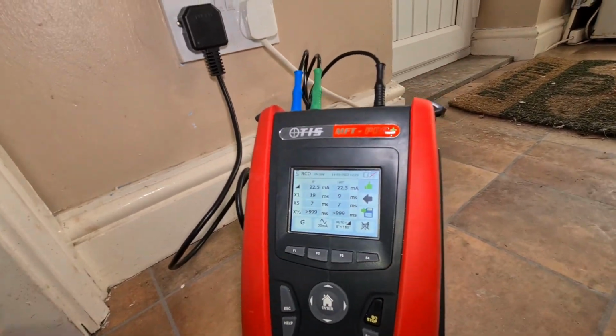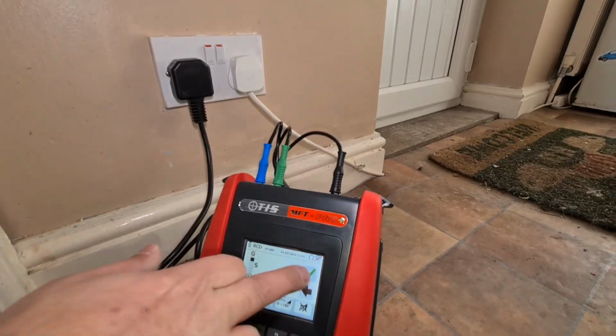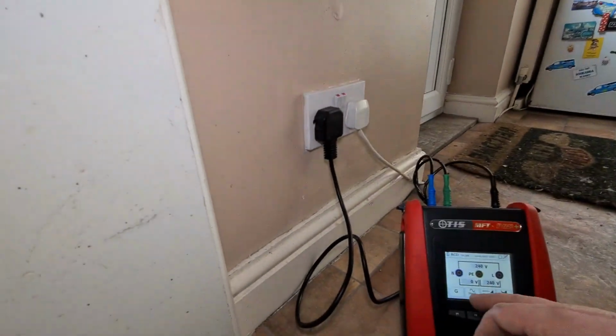There is a bit of a fuss over RCD testing, and if you go off and look at the EICR channel, they had, I think it was Luden, Megger and the ECA on to talk about RCD testing. In terms of complying with regulations, you only need to test your RCDs as if they were a type AC. However, if you are aware that there could be some DC leakage affecting things within that circuit and you've got a type A RCD, you might also want to test it in the type A mode as well, but you're not obliged to do so.